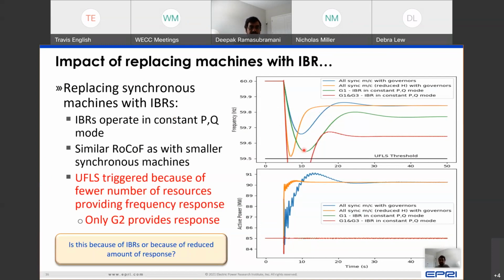You can have inverters in constant power mode. You can have an increase in the number of inverter-based resources, again with constant power mode, which means grid following, and they're not providing frequency response service to the system, just conventional primary frequency response service. And UFLS is triggered because ultimately, in this red curve, there is only one source remaining to provide frequency response.